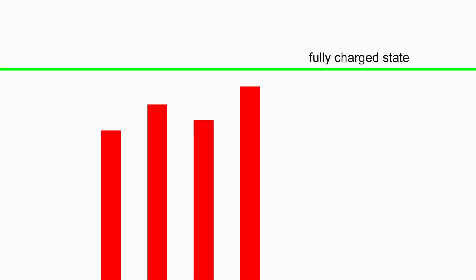So what the BMS does is charge the whole battery until the section with the highest voltage reaches the limit, then discharge that section a little, then charge the entire battery again, discharge the high section again, and repeat until you reach the same equal voltage on all sections. This is what the BMS does.